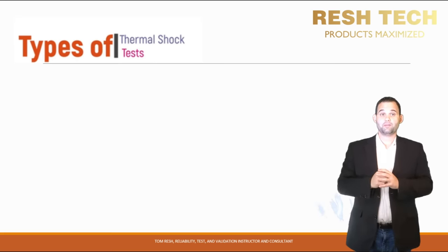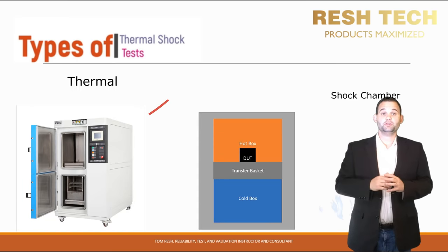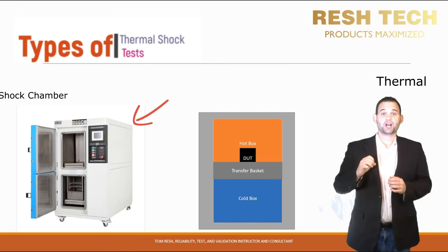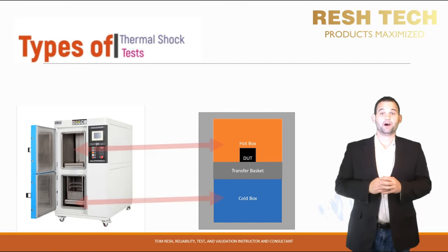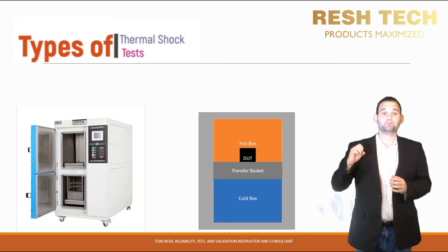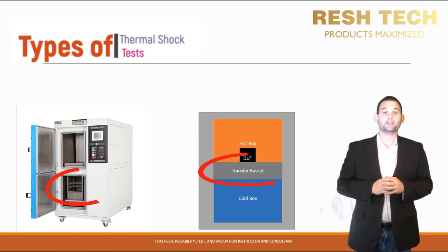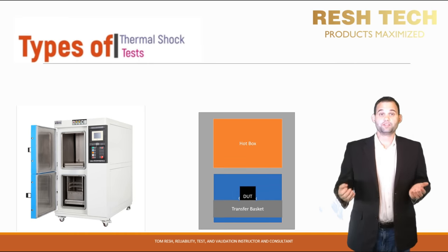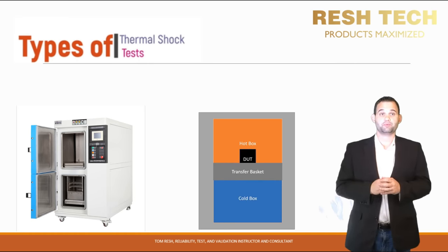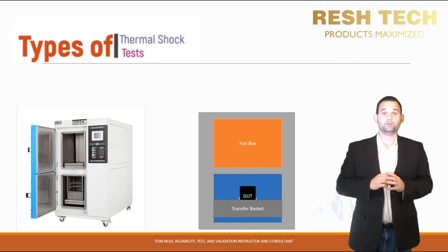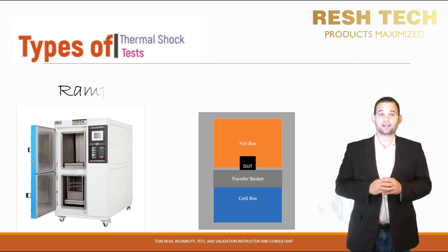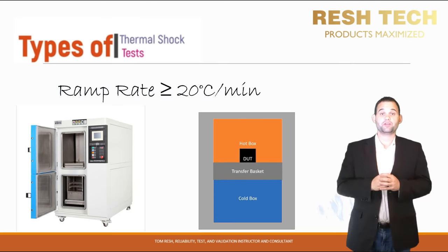There are several methods to accomplish this. The first is to use a specialty chamber called a thermal shock chamber. Thermal shock chambers have a hot and cold box. A test part or system is placed in what is called a basket, which transfers either vertically or horizontally depending on your chamber type between the hot and cold boxes. Typically, the transition between hot and cold boxes happens at a ramp rate greater than or equal to 20 degrees Celsius per minute.